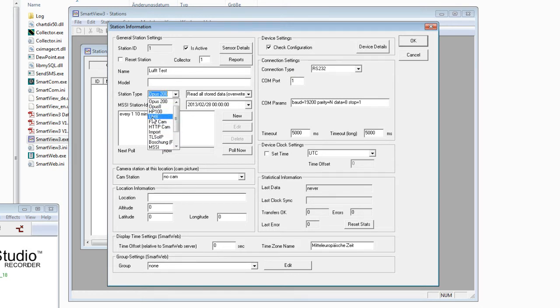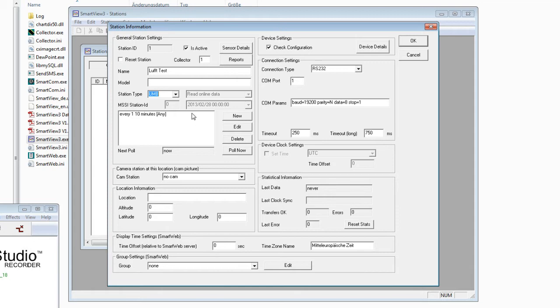You have to choose the right station type — in this case a UMB station. The poll time standard is every 10 minutes, but you can change this to your needs. You can also link a camera station, enter local information, and access device settings. When polling the station for the first time, you always need to use the Check Configuration button.